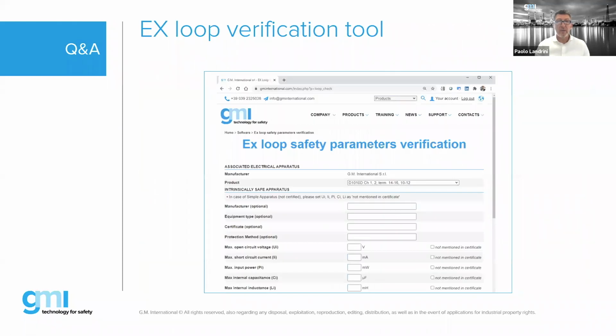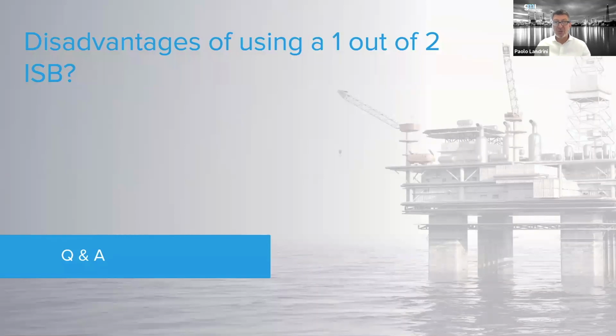Okay, here we are. We put online a tool called the EX Loop Verification Tool, where you can enter the parameters of your field device. The one for the barriers is automatically uploaded, and it will tell you okay or not okay. Everything depends on the length of the cable, which must be specified, and the type of instrument used. Of course, all has to be matched to the area classification. So depending on where you're going to install the barrier and the transmitter, these parameters change. It sounds complex, but it's not very much so, because all manufacturers of safety barriers know what instruments are available in the field. Now we have a standardization of these parameters, so they are basically all the same. 99% of the time they are okay, unless you're talking very long distance. Okay, let's move forward, otherwise we have a lot of other questions.